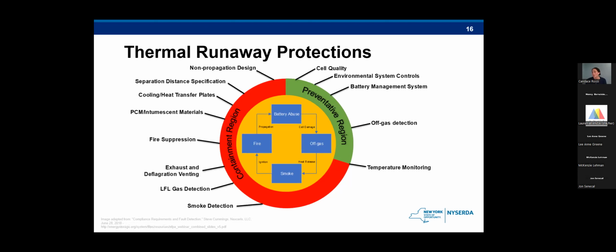So this slide shows the same image, but now with the thermal runaway protections that are embedded into projects and are required by the Uniform Code as well. So in the preventative region, this is where the quality of the cell or the environmental system controls may prevent thermal runaway. As we spoke about before, the battery management system will be able to detect the system is not operating correctly and may be able to isolate the issue prior to it propagating to the next cell.